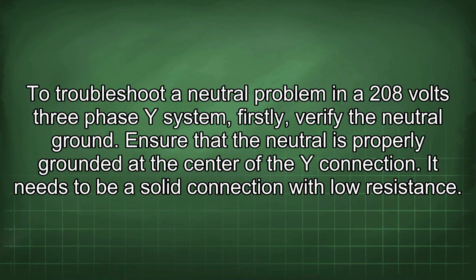To troubleshoot a neutral problem in a 208 volts 3-phase Y system, firstly, verify the neutral ground. Ensure that the neutral is properly grounded at the center of the Y connection. It needs to be a solid connection with low resistance.